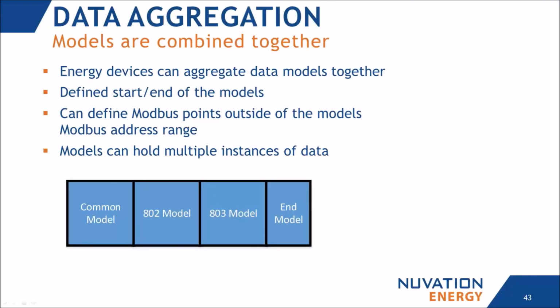I want to go into a little bit more about what these models mean and how they're used. Really, these models - there's a structure within SunSpec that allows you to combine the models. It defines a start and an end to the models, so it starts at the common model and ends at the end model. There's no restriction that you use SunSpec only - you can find Modbus points outside of this model range. You can scan a Modbus map and find models by their definition, so that standard is well set up.